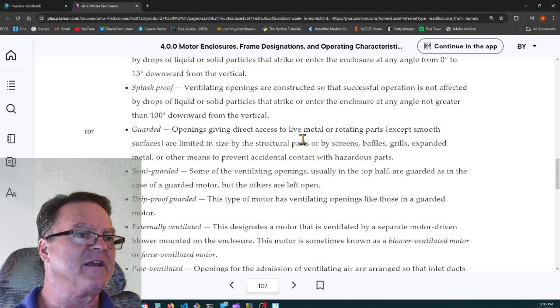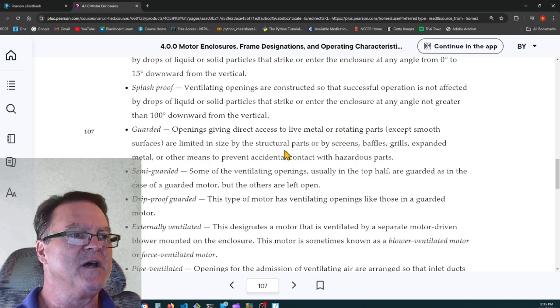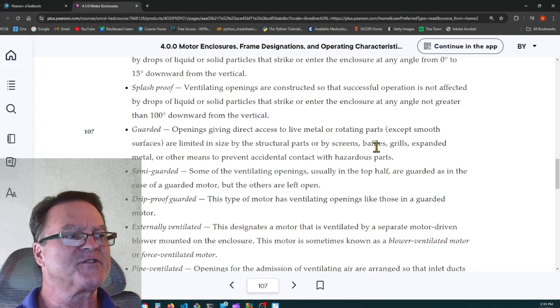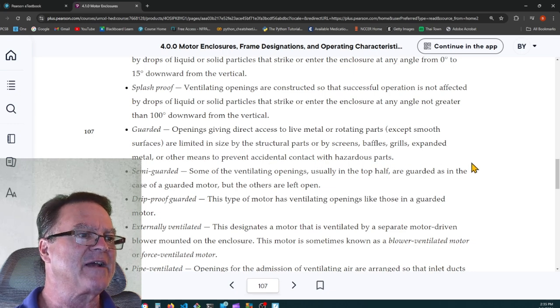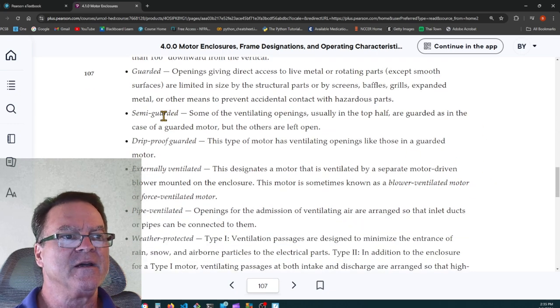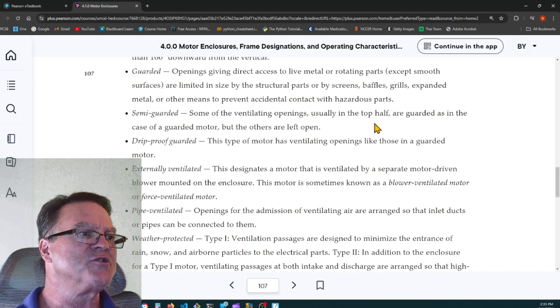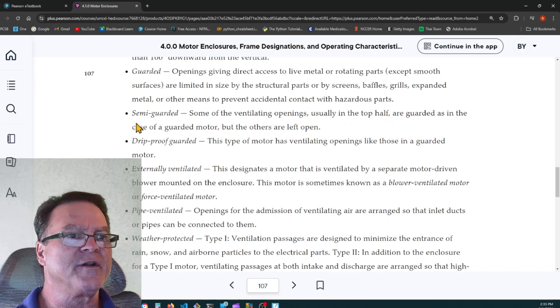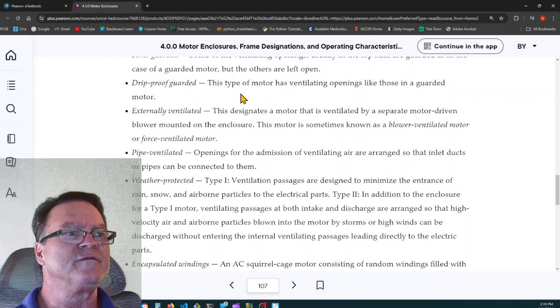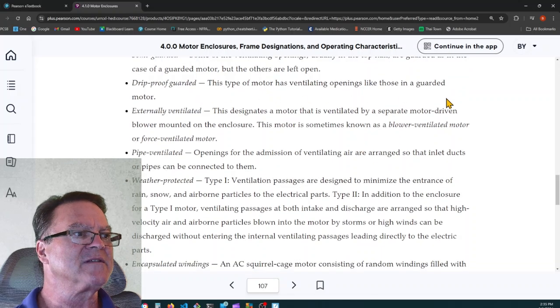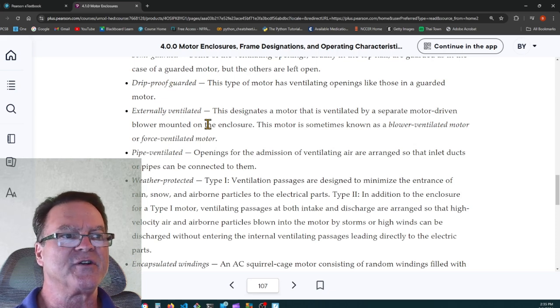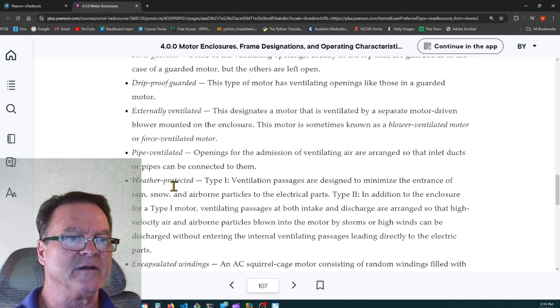Guarded, the openings giving direct access to the live metal or rotating parts are limited in size by the structural parts or by screens, baffles, grills, expanded metal, or other means to prevent accidental contact with hazardous parts. Semi-guarded, some of the ventilating openings, usually on the top half, are guarded, as in the case of a guarded motor, but the others are left open. Drip proof guarded, this type of motor has ventilating openings like those in the guarded motor.